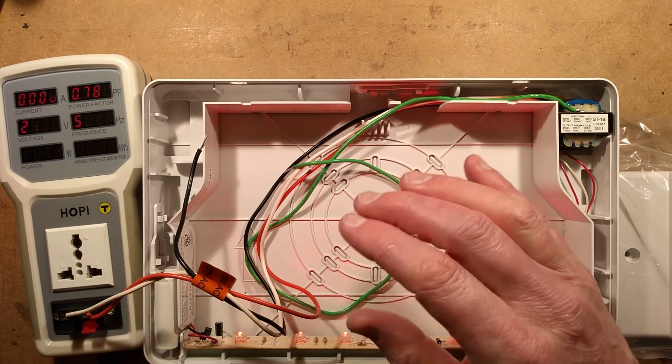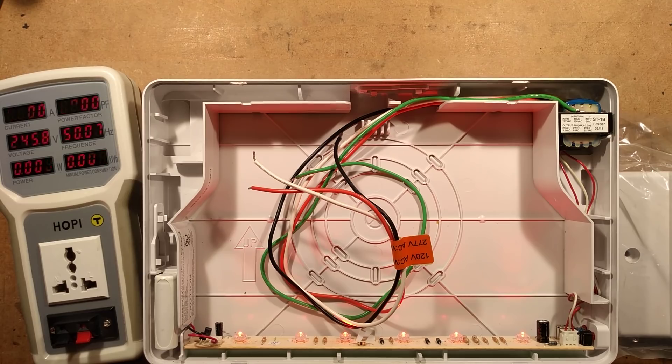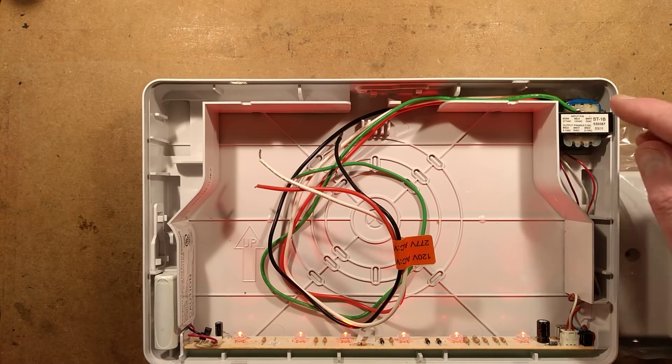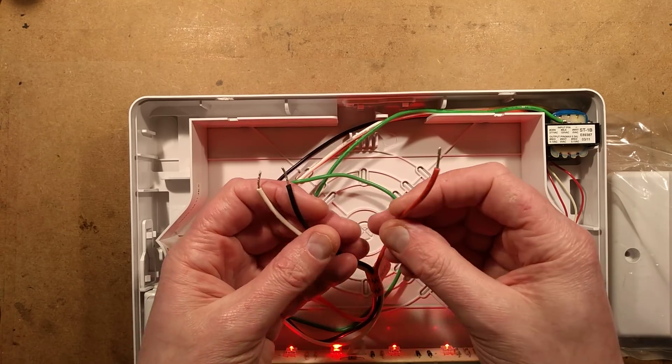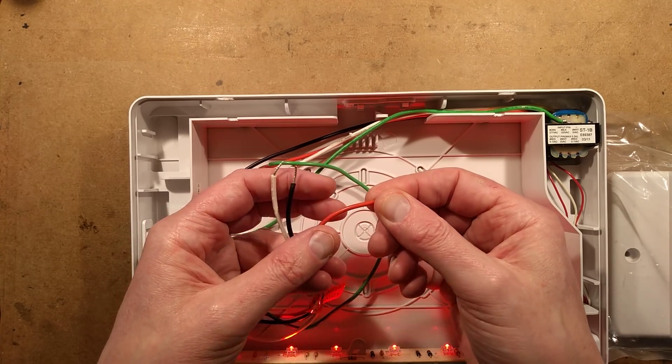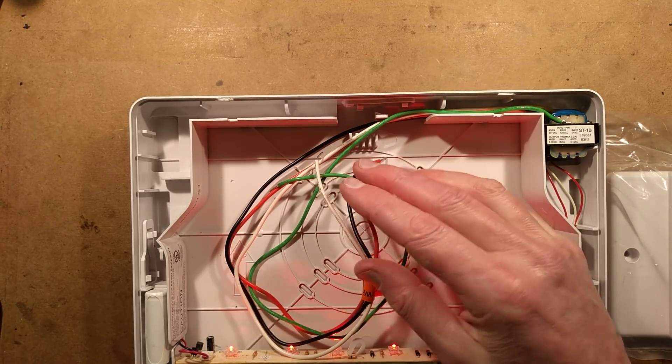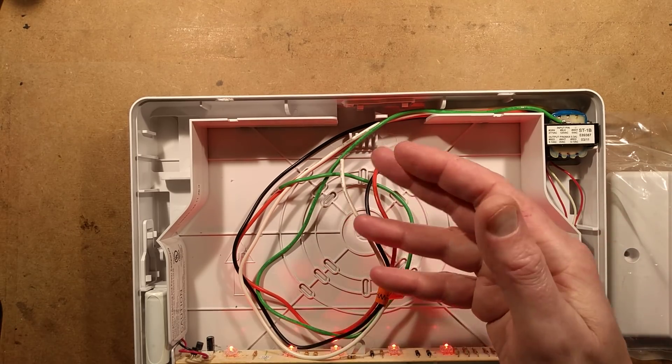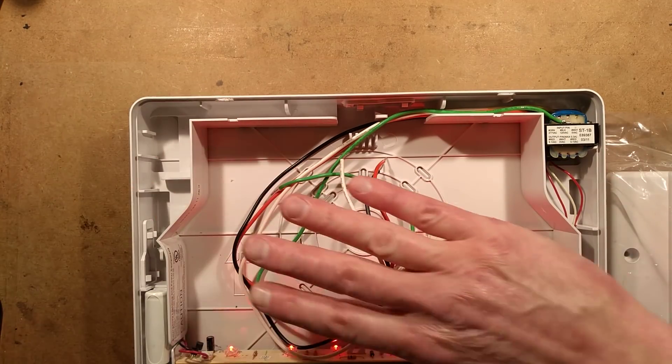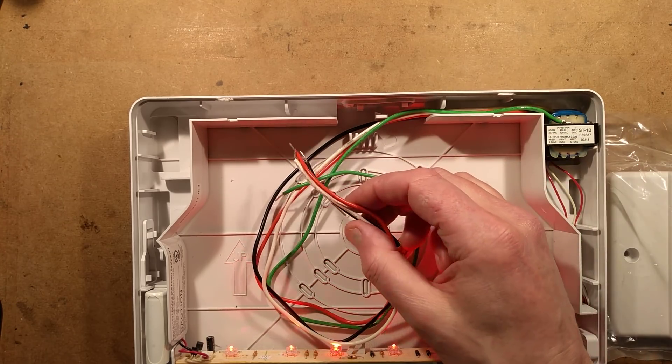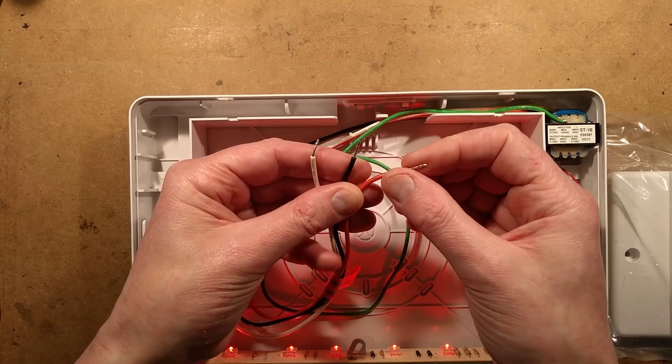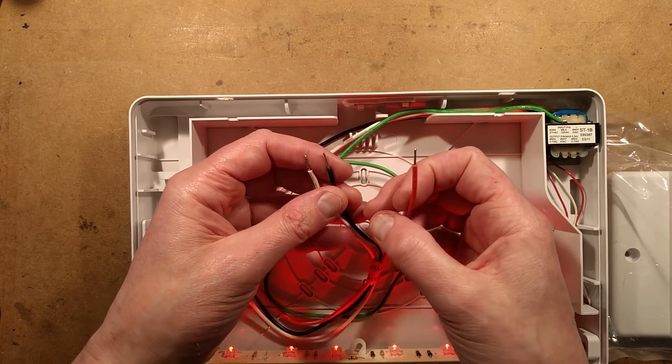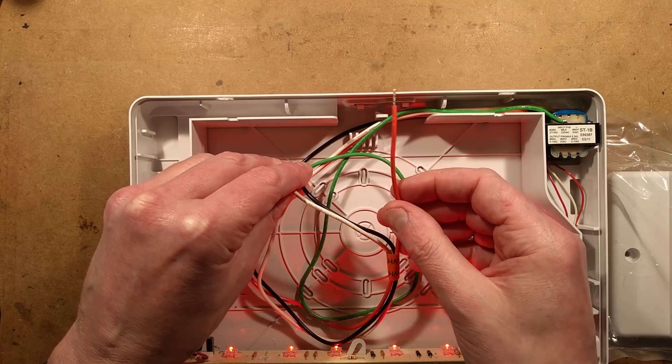This works the other way—if you connected this to a 120 volt supply and left the orange wire hanging out, it would become live at 277 volts. I'll tell you about a horrible accident at a fairground. A maintenance guy installed a new transformer in one of the cars. The transformer had loose wires, and he connected it to a 120 volt supply but left this wire lying loose. It effectively came live at 277 volts and touched the metalwork, spot welding itself on.